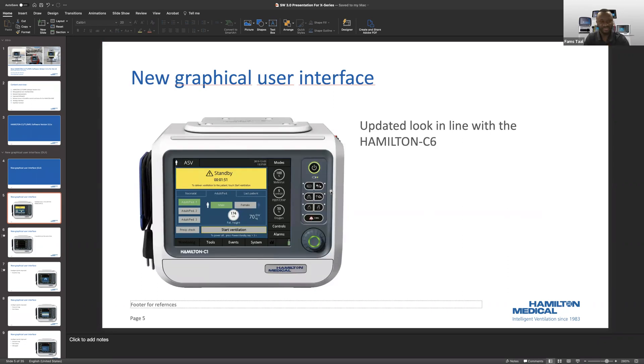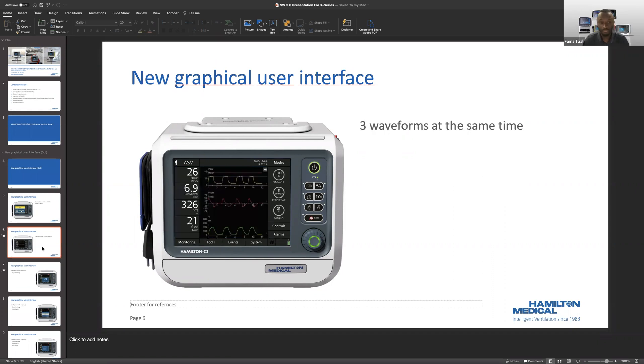On your graphical interface, if you're comparing the 2.0 device with a 3.0 device, you will see the background is darker versus blue, and the tone of blue will show some differences in visuality. One of the biggest updates is that on the 2.0 software you only had two waveforms — you could put pressure, change flow to volume, or volume to flow. The newer software gives you the opportunity to see three waveforms. You will see pressure, flow, and volume without having to sacrifice one for the other.